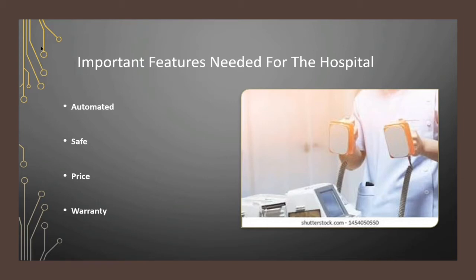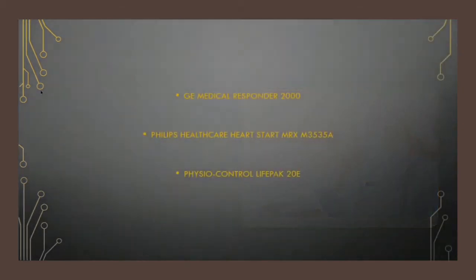Automatically analyzes the heart rhythm to determine whether a shock is required. Automated self-test that tests the device circuit and software connection to AC power, electrodes, batteries, and discharge capabilities. Pacemaker cables should be at least 1.5 meters long to allow convenient positioning in various patients' locations. Price and warranty need to be considered as well. Facilities should look for the best offer of manufacturers. These are the three alternative types of defibrillator: GE Medical Responder, Philips Healthcare Heart Start, Physiocontrol Life Pack.